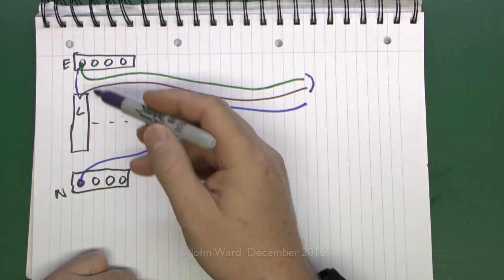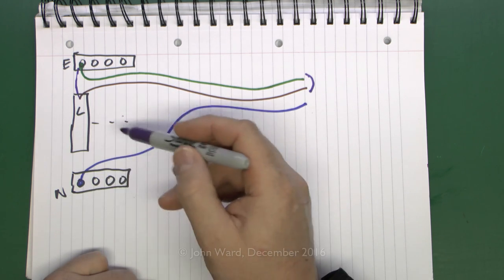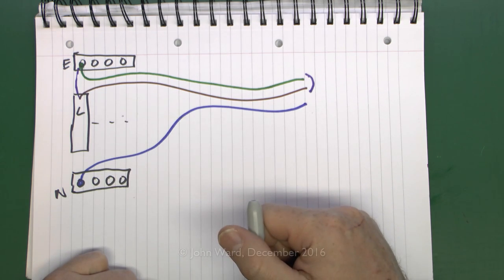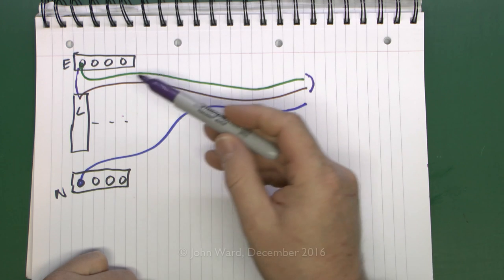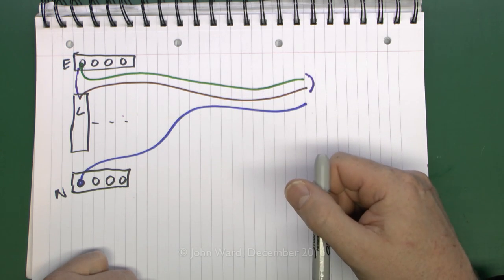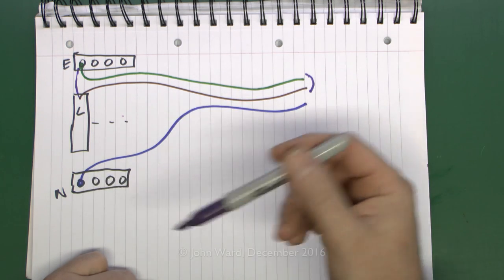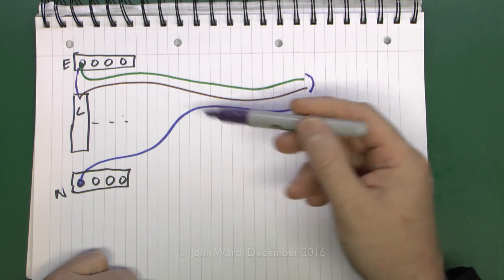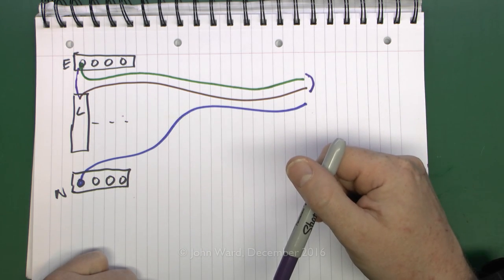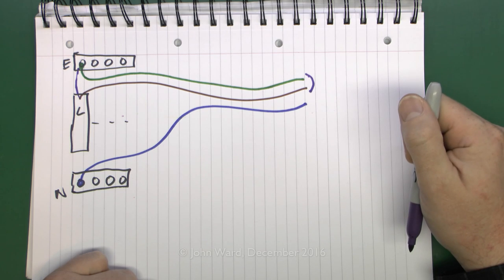But even if you have done that, you still need to make sure that the supply coming into the building is connected correctly inside the consumer unit. Otherwise you could end up with the entire installation connected with the wrong polarity, or in other words line and neutral reversed, which would override any of the previous tests you've done. You'd end up with the entire thing incorrect.